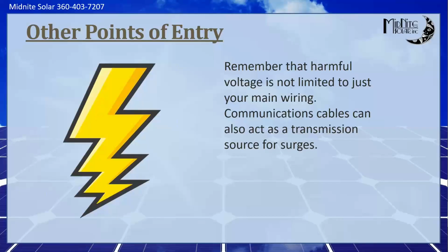You start coming in on the communications and you're on the low voltage side and it just goes through everything. So if you're doing Ethernet like that and you want to run Ethernet a long ways, you can buy them on Amazon. They're relatively cheap. They are Ethernet to fiber optic converters. So you can buy a pair of these for like $60, and then you buy a fiber optic cable to go between them, and now you've optically isolated the equipment.